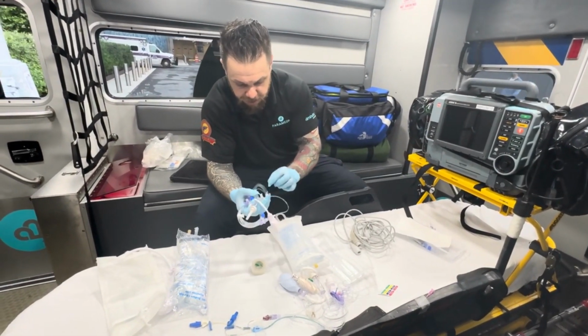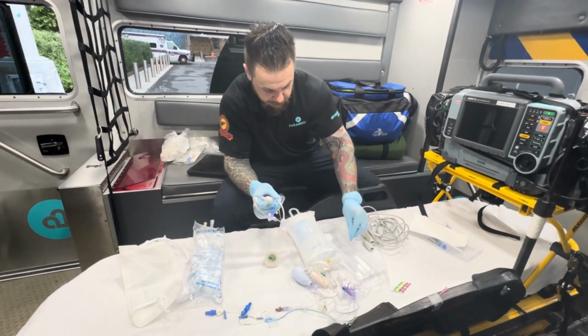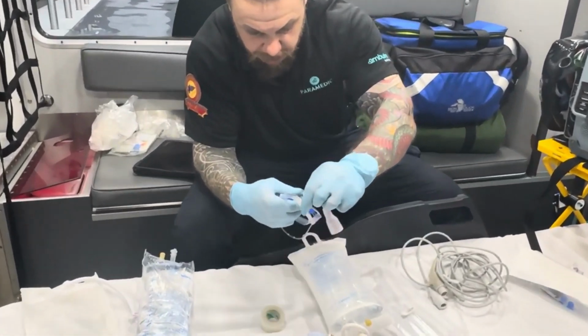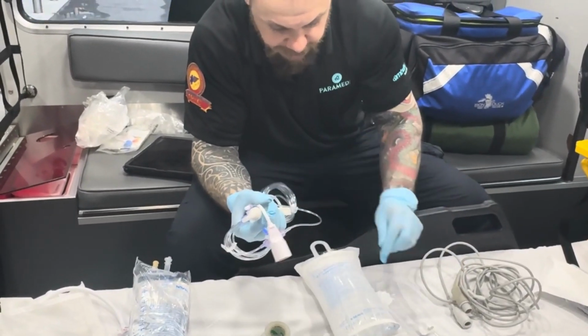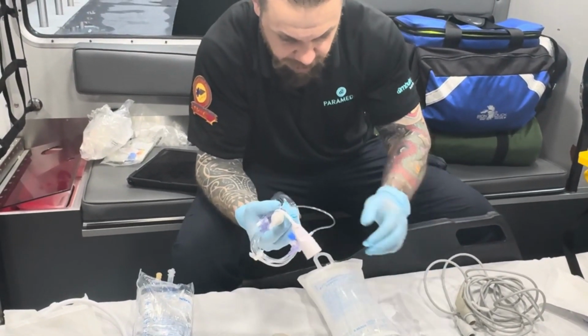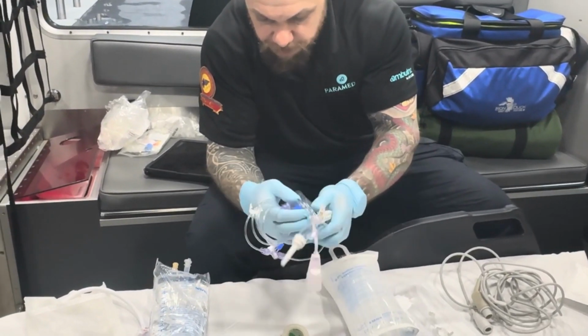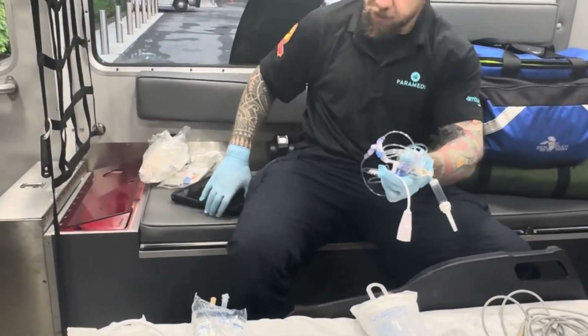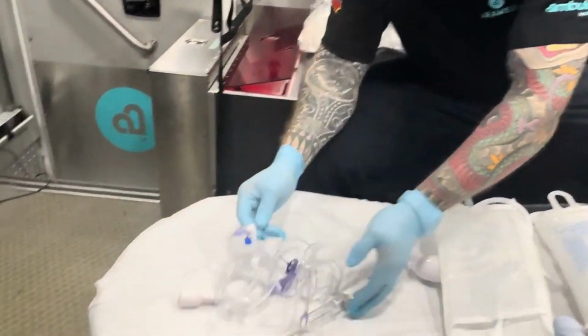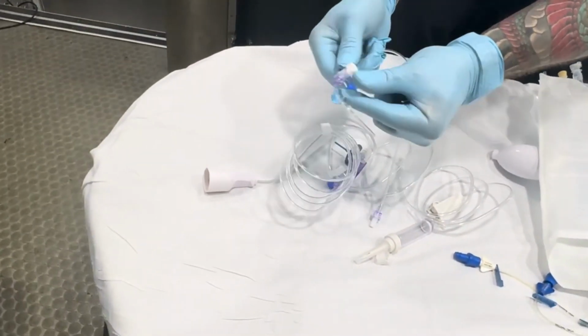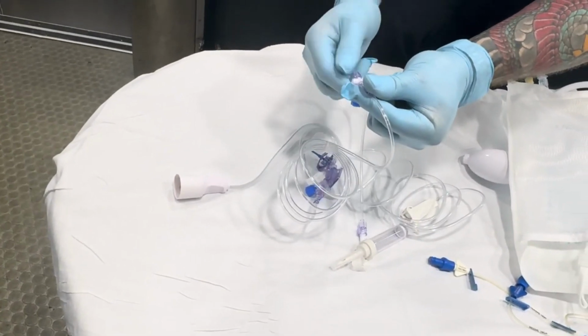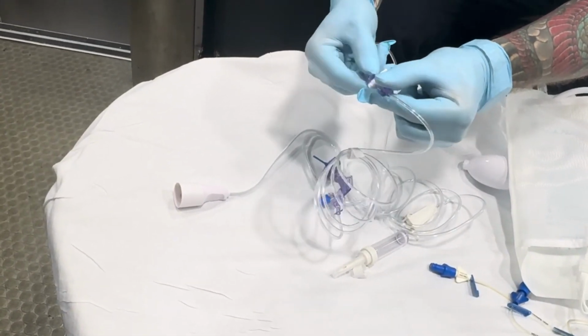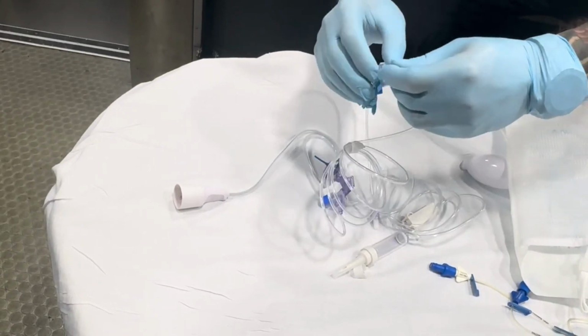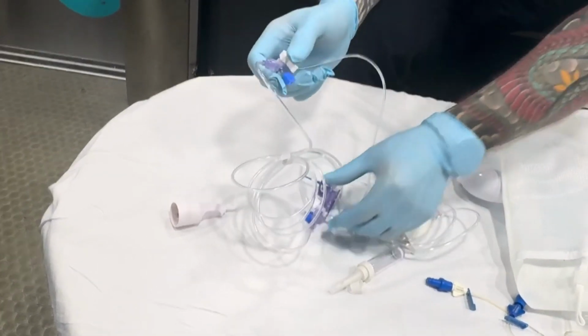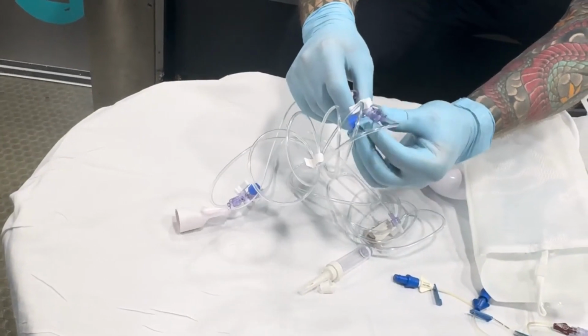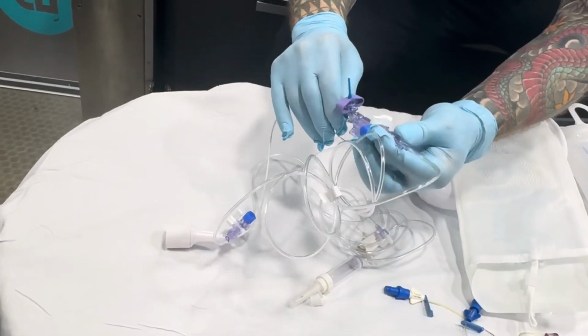The next thing I do is, when I take this out, I take all the stickers off, and I usually just put it in the box. And always check from the factory if all your connections are actually tight. So which connections am I referring to? If I come over here so you guys can get a clear picture, this is what I'm referring to. These portions right here. See how it's loose? You see how it's dangling about? If you start to flush your fluids, you will have fluids squirting all over the place. So I always check that this is connected, and then this is your actual transducer. Again, it's loose. I want to make sure it's tight.